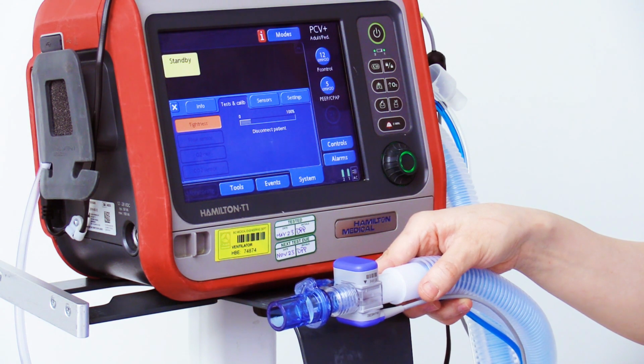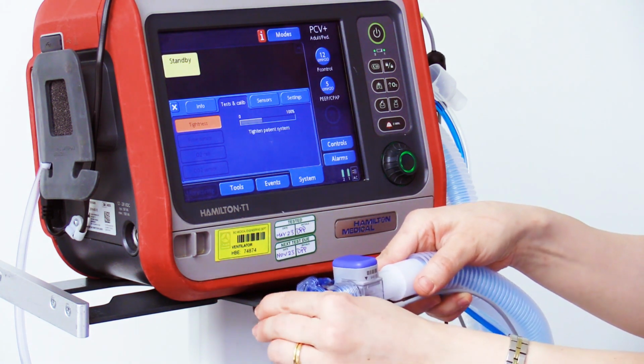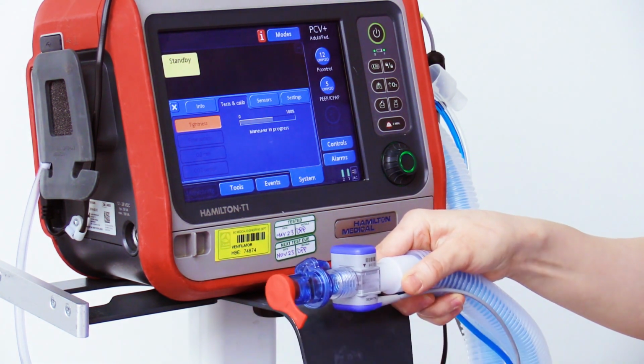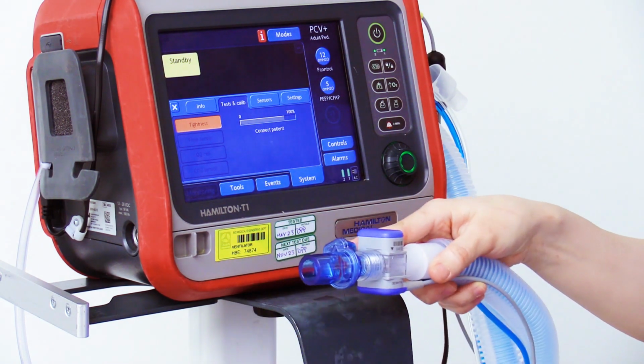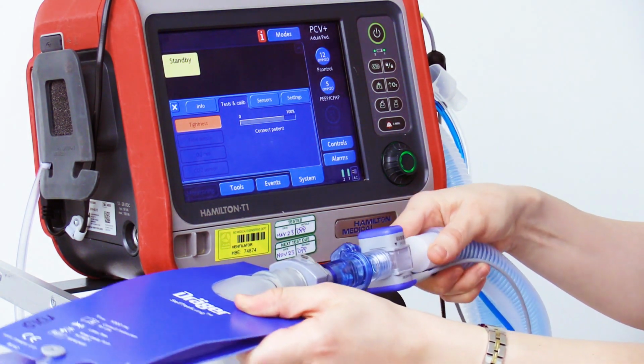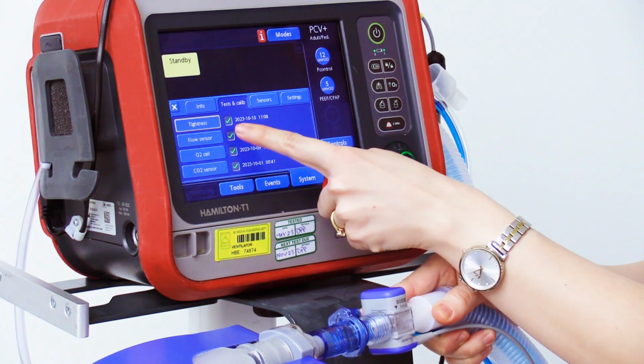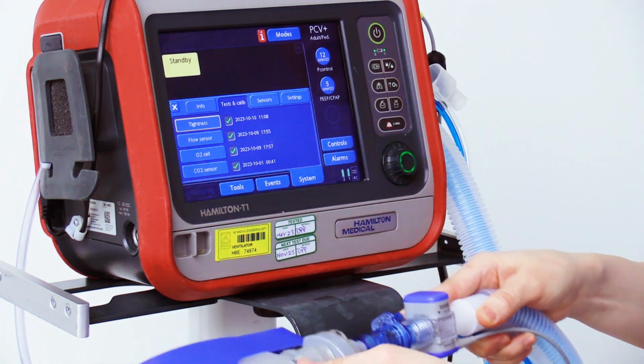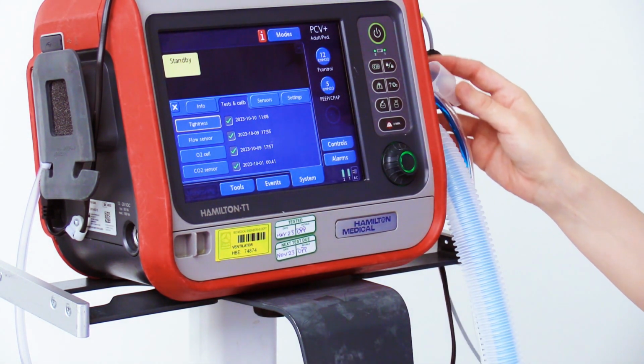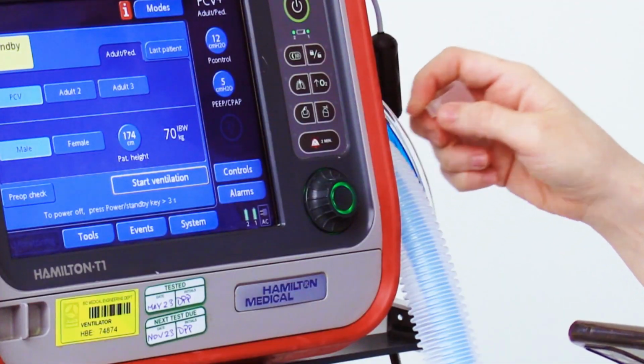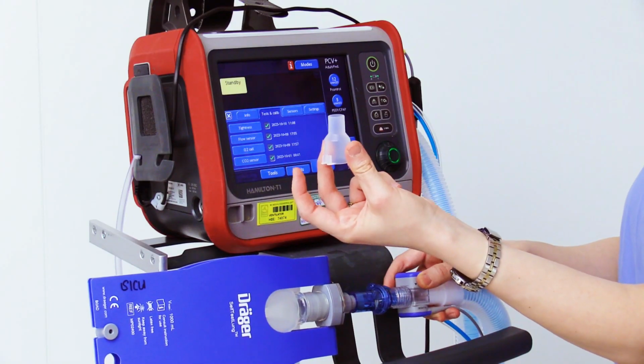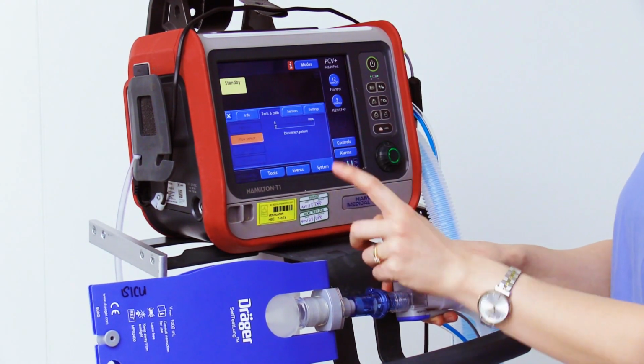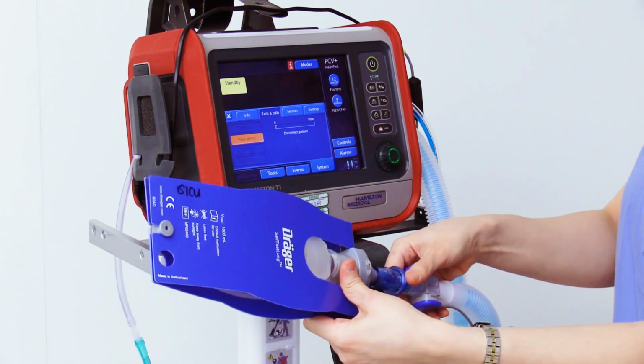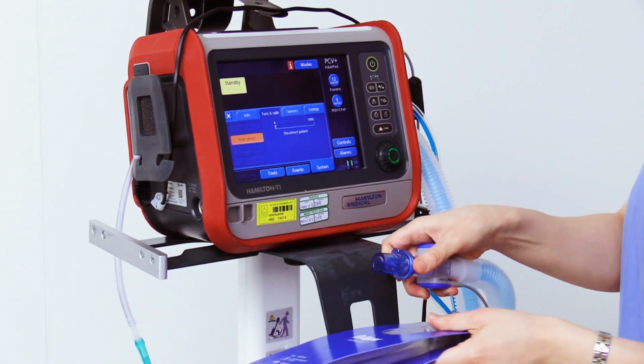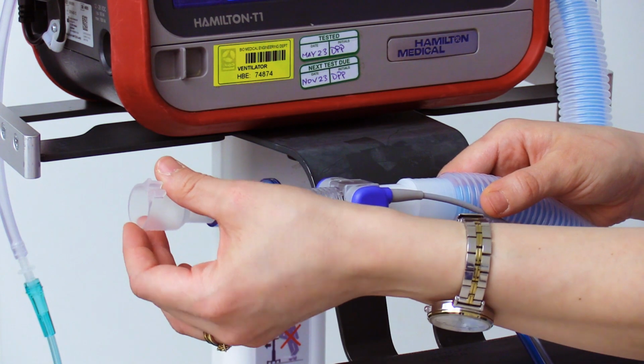Once instructed, block the opening and upon further instruction, reconnect the circuit to the patient or test lung. A green checkmark will indicate that it is calibrated and ready. To calibrate the flow sensor, you will need the adapter provided with the circuit. Select the flow sensor calibration function and follow the instructions. Begin by disconnecting the patient, then attach the adapter to the flow sensor.